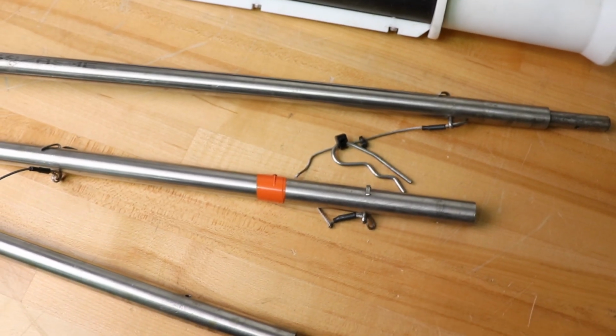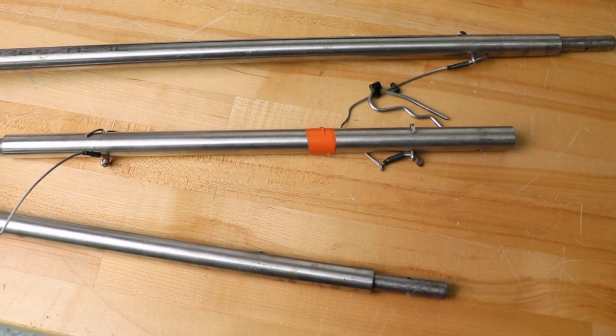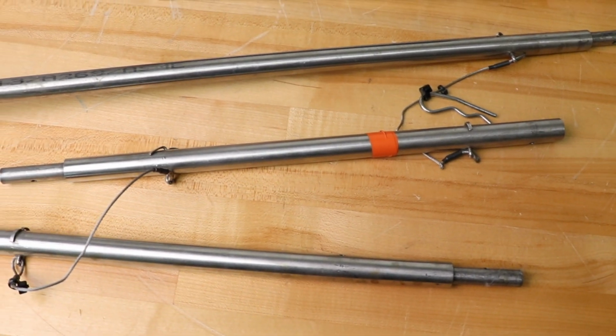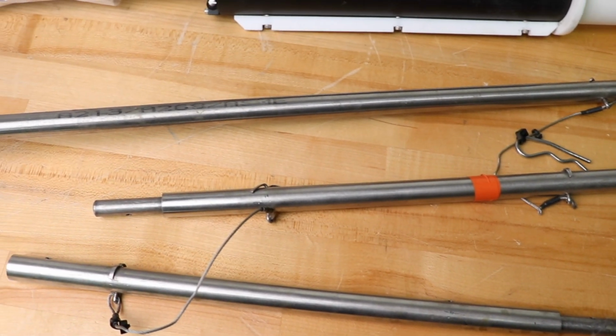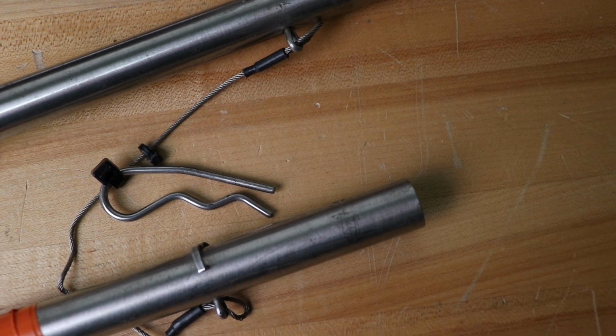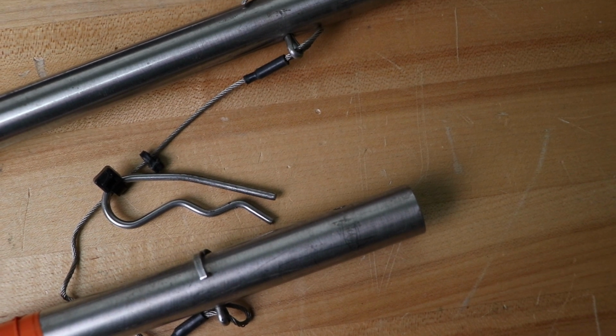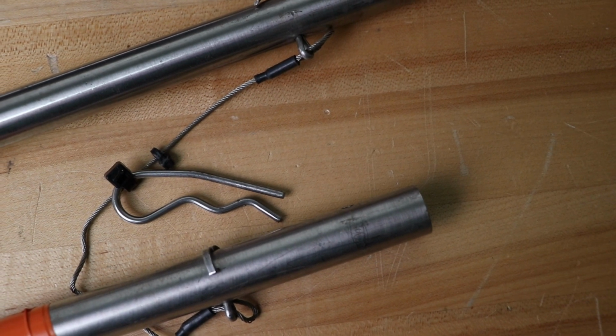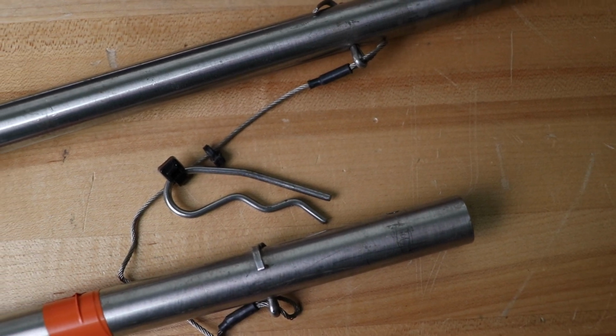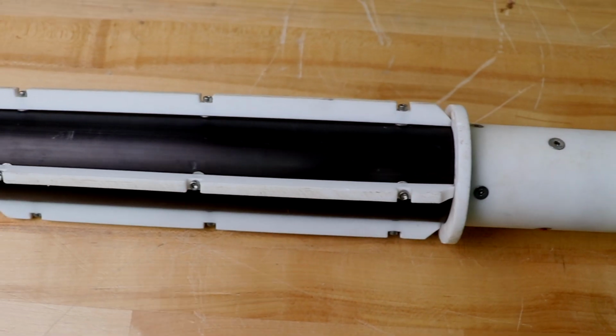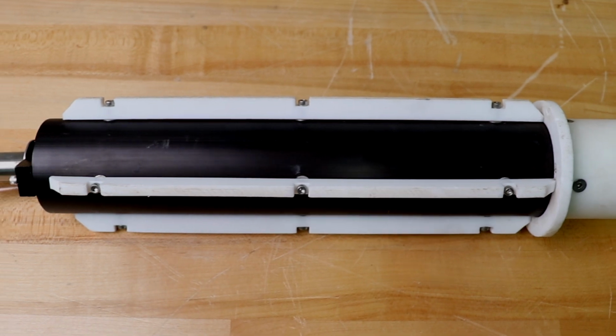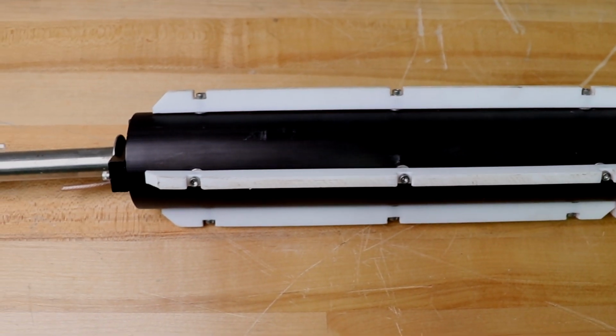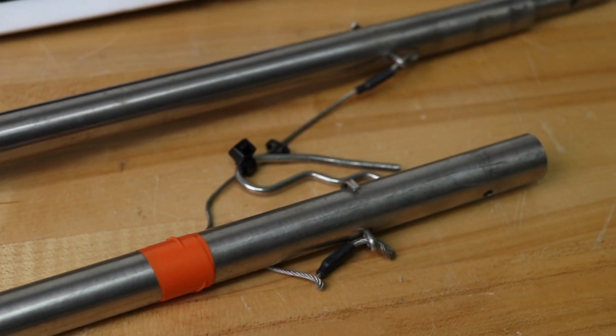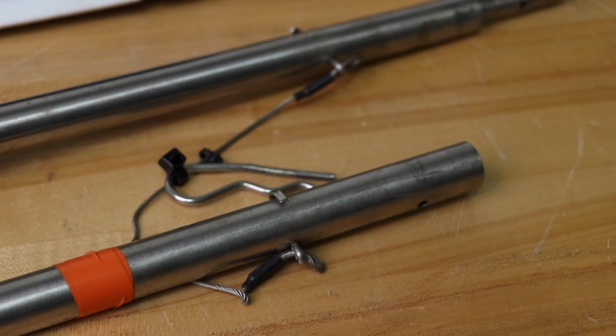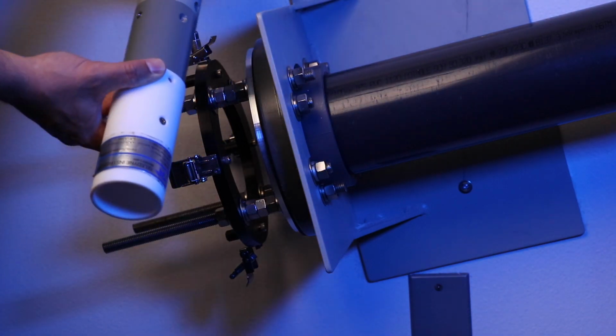For stacks with an annulus or thick outer wall that must be bridged by the UltraFlow 150 purge nozzle assemblies, TML offers the link rod option. This option is required for all units where the purge nozzle assembly would exceed 72 inches. The link rod assembly consists of a transducer housing with skids to center it in the port, and a series of short rods that connect or disconnect as the transducer housing is inserted or removed from the port.